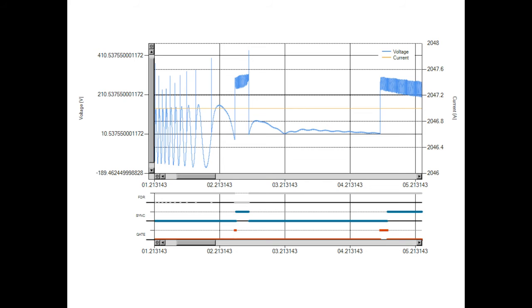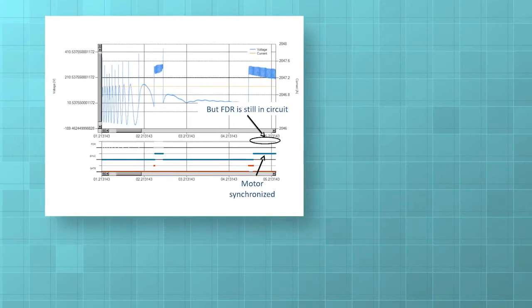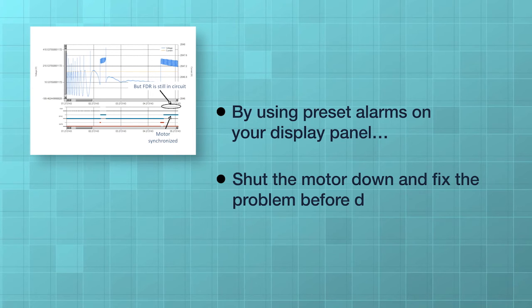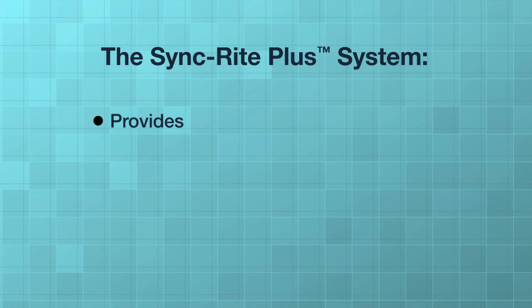By identifying these problems graphically, you can provide a quicker diagnosis of the root problem and reduce your downtime. This screen shows the status of the field discharge resistors, also known as FDRs. If the FDRs stay in the circuit after a motor synchronizes, they can burn up.